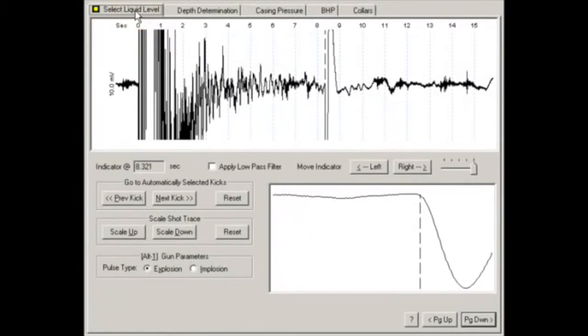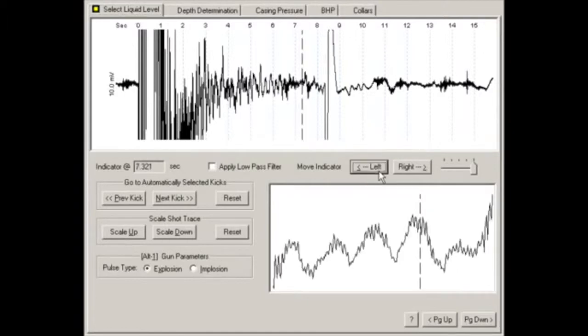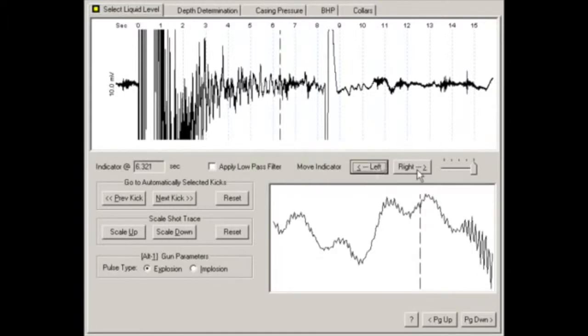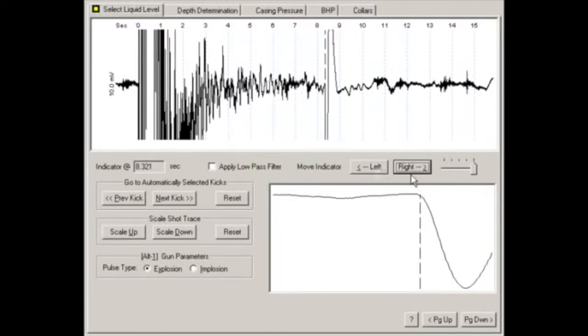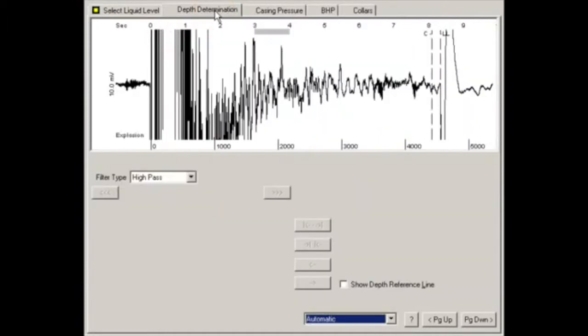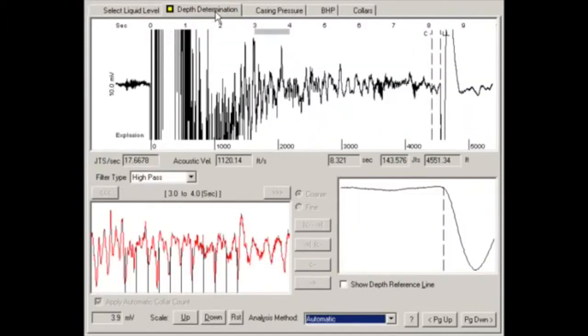TWM has calculated and selected an acoustic reflection as the best liquid level. Use the left and right arrow buttons on the screen to fine-tune the selected liquid level. The box in the lower right shows a close-up view of the selected liquid level. Now go to the Depth Determination tab. Here TWM displays the calculated depth to the previously selected liquid level, which is indicated by a vertical line labeled LL.